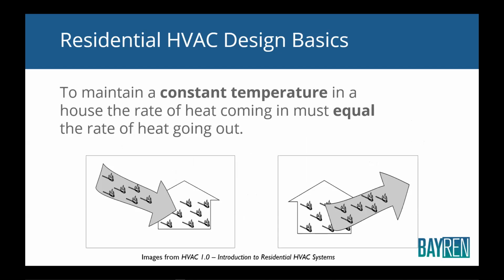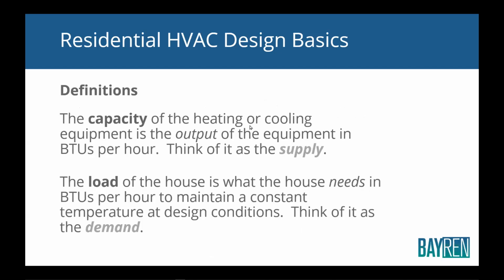It's going to run for a little bit, shut off, run for a little bit, shut off, run for a little bit and shut off. And it's inefficient, just like it would be driving that way. Imagine driving down the freeway and slamming on your brakes every mile and then starting up again and then stopping and starting up again. That's exactly what short cycling is like in terms of efficiency. There's also a lot of comfort issues, and I'm going to show you some interesting graphs in a few minutes, okay? So the capacity of a heating and cooling equipment is the output of the equipment.